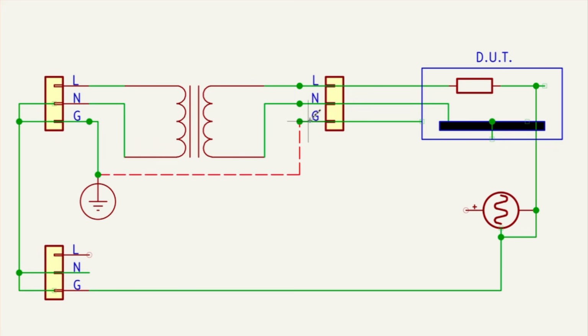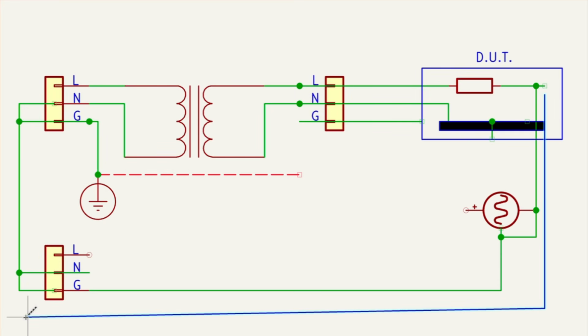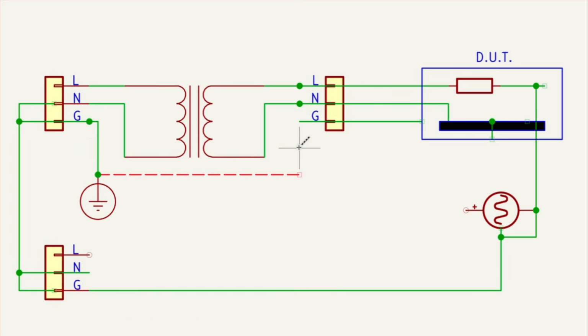Now take the scenario where this ground wire is actually cut, which is essentially what I did. With the probe here, ground reference at the mains, the ground path has been broken. There's nowhere for the loop of current to flow — we're stuck. Because of that, we don't have a short across the live and the neutral, and that's what we want.